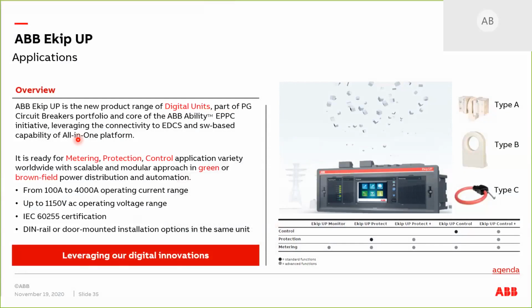So with this one, the EKIP Up is available from 100 amperes to 4,000 amperes of operating current range. We do some retrofit and put the EKIP Up on the working breaker, but the trip logic of that working breaker will be transferred to this EKIP Up. And then for the current sensors, we have type A, type B, and type C.